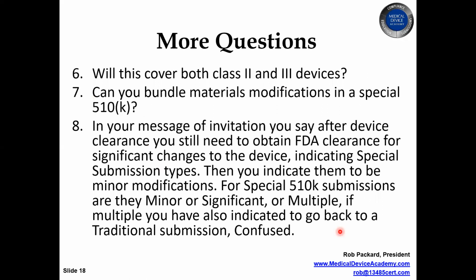Question 6, will this cover both class 2 and 3 devices? I don't know whether the person meant this presentation or special 510Ks. However, there are only about a dozen device classifications that are class 3 that are eligible for 510Ks. And I think almost all of those require a clinical study. So if you have a class 3 device and you have clinical study requirements and you're making modifications, you're probably talking about a high enough risk device here where the FDA may not feel comfortable with this being a special 510K.